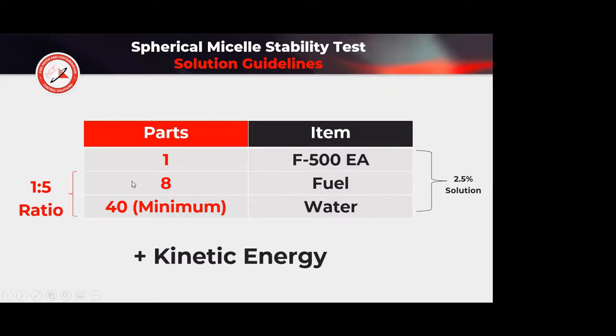This is a very important ratio too, because 8 parts of fuel to 40 parts water reduces down to 1 to 5. So this will allow, and we'll see this in the next edition of the standard, the fire department to say, oh, I got 20 liters of fuel spilled on the ground. They can easily say 20 liters times 5, that gives me 100 liters. So now if I lay down 100 liters of a 3% solution, not a 2.5, but a 3% solution, I've actually applied 3 liters of F500, and each liter can encapsulate 8 liters of fuel. So 3 times 8 is 24.